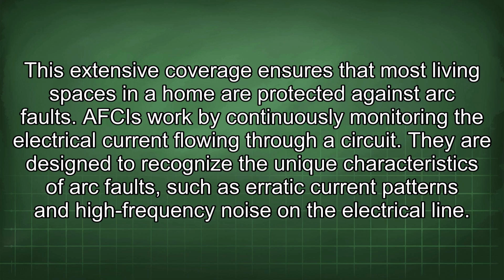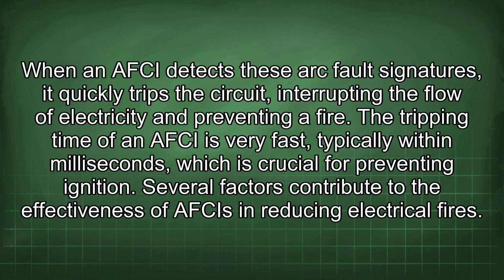AFCIs work by continuously monitoring the electrical current flowing through a circuit. They are designed to recognize the unique characteristics of arc faults, such as erratic current patterns and high-frequency noise on the electrical line. When an AFCI detects these arc fault signatures, it quickly trips the circuit, interrupting the flow of electricity and preventing a fire. The tripping time of an AFCI is very fast, typically within milliseconds, which is crucial for preventing ignition.